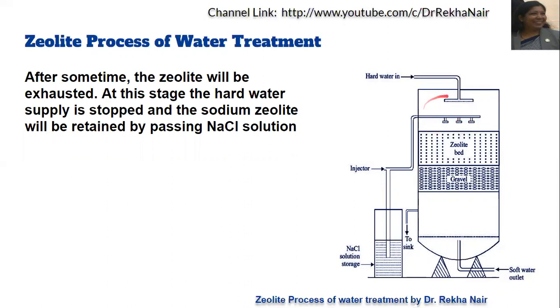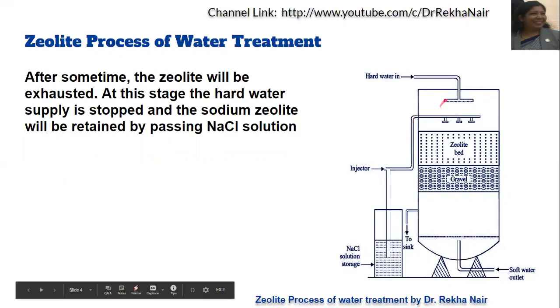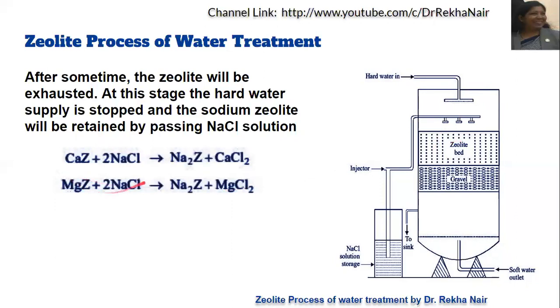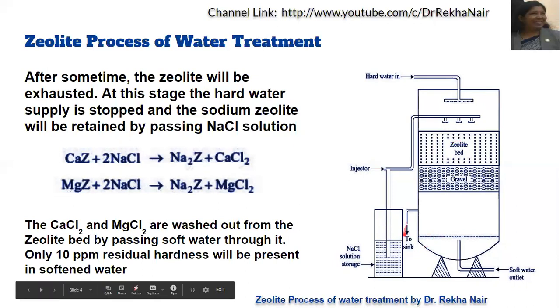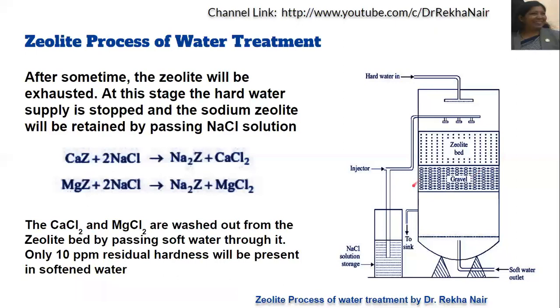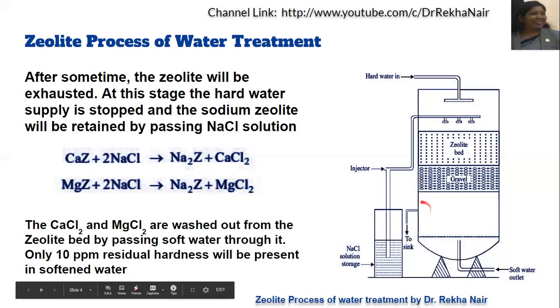To regenerate, we stop the hard water supply and pass a sodium chloride solution through the bed. The outlet is also closed. We then inject the sodium chloride solution, which reacts with the calcium and magnesium zeolite present in the bed and converts it back to sodium zeolite. We get sodium zeolite back, and the byproducts — calcium chloride and magnesium chloride — are washed out from the zeolite bed by passing soft water, and the calcium and magnesium ions are sent to the sink.